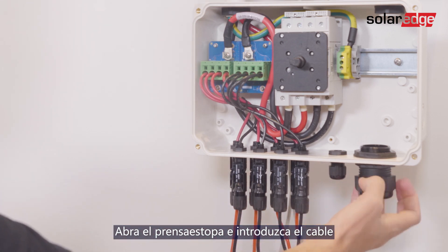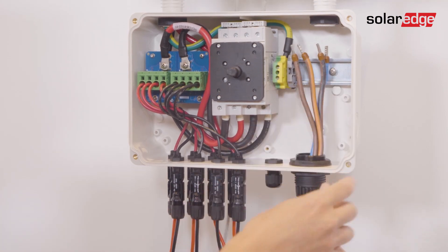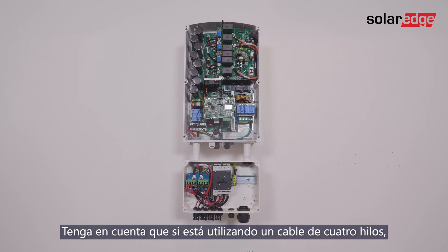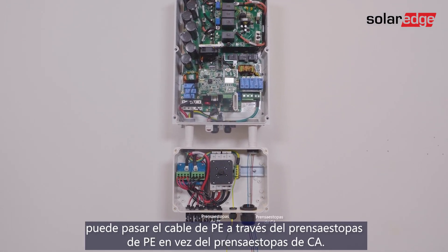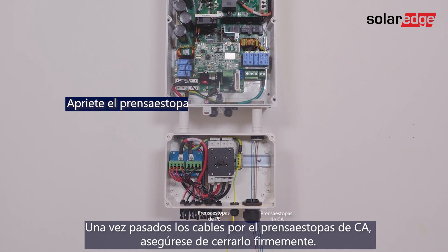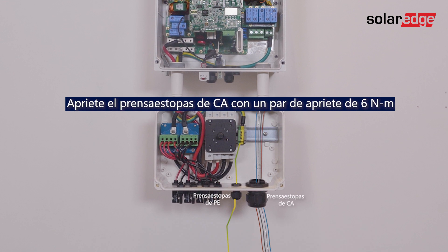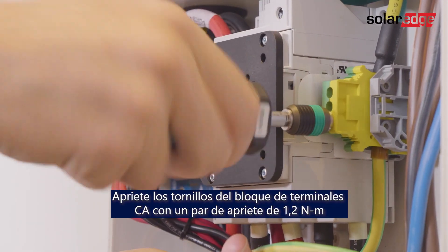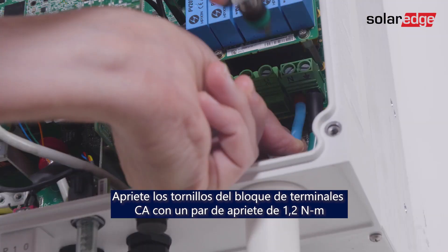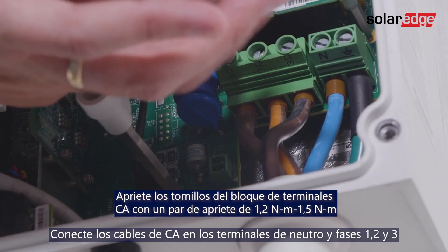Open the gland and insert the cable. Note that if you are using a four-wire cable, you can pass the PE wire through the PE gland instead of through the AC gland. Once the wires are passed through the AC gland, make sure to firmly close it. Then connect protective ground to the PE terminal. Connect the AC wires to the neutral, line 1, line 2, and line 3 terminals.